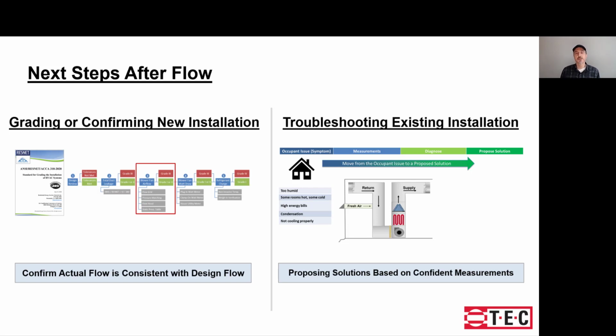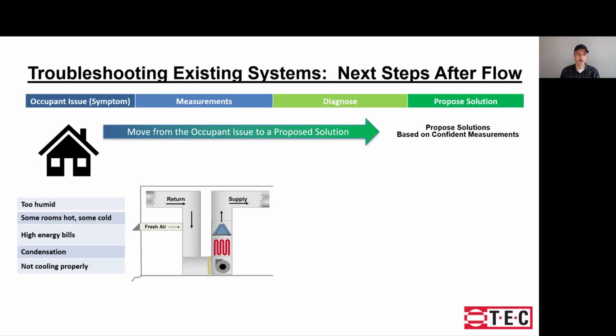In an existing installation where we're troubleshooting, it's a little bit more involved, so let's talk about that for a minute. In these cases, perhaps we're invited in because the homeowner or occupant is having a comfort or performance issue, like some rooms are hot, some rooms are cold, or maybe there's humidity or moisture condensation issues. In that case, what we want to do is propose a solution that's really going to solve the problem, and that means that measuring airflow alone probably won't give us an indication of what the root cause is. We need to make some other measurements before we propose our solution.